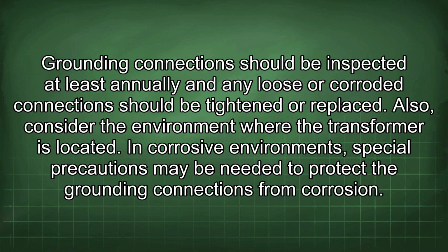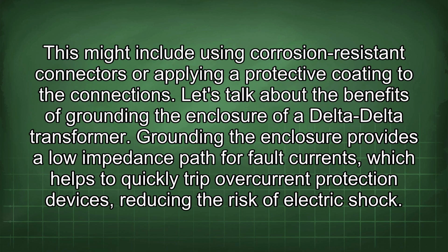Also, consider the environment where the transformer is located. In corrosive environments, special precautions may be needed to protect the grounding connections from corrosion. This might include using corrosion-resistant connectors or applying a protective coating to the connections.